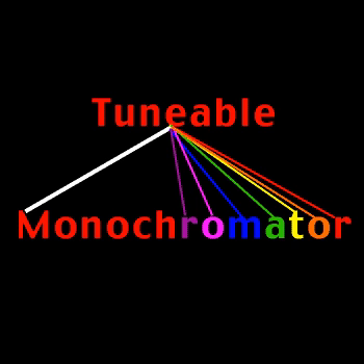The amount of light absorbed at a specific wavelength reflects the amount of analyte in a sample. Although there are many different versions of monochromators, the design we'll examine here is called a Czerny-Turner design. It uses two slits, two mirrors, and a grating.